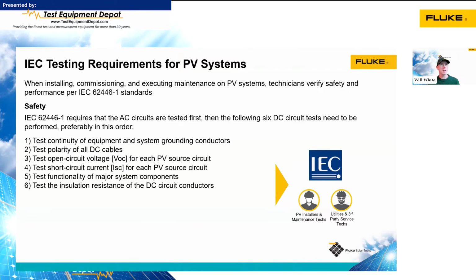For the safety tests, they require testing of the continuity of the equipment grounding conductor, so making sure our metal parts are actually bonded together. We're testing polarity, voltage, and current of all of our PV circuits. We're going to test to make sure all of our components are functioning properly, the disconnects work, breakers are working properly, the inverter is working properly. And we're going to do insulation resistance testing of the DC conductors to make sure that the insulation hasn't been compromised. Now, performance testing includes IV curve tracing and thermal imaging as well to make sure the system is actually operating the way it should be.